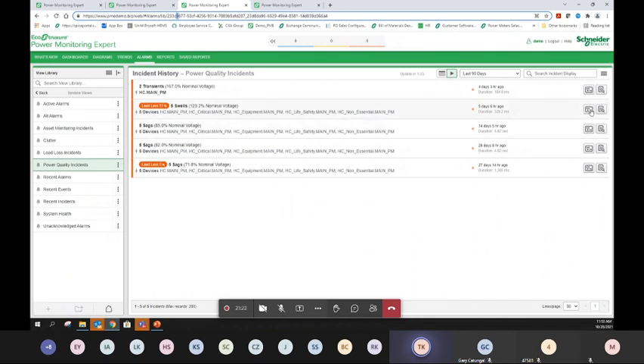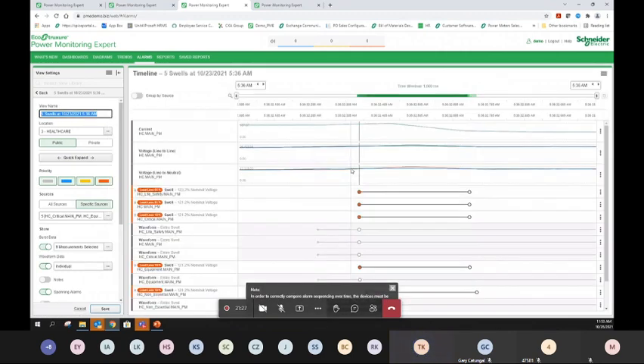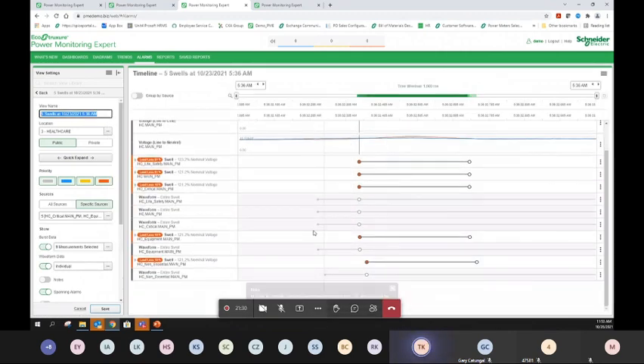If you look at the timeline view, this is one of the key selling points that we have. The first 4 faults happen at the same time, actually one related to another, and the last fault is here. You have to look at the first fault that happened - it comes from the main safety life safety incomer and ends at one of the non-affected areas. The software will also automatically calculate the load loss.